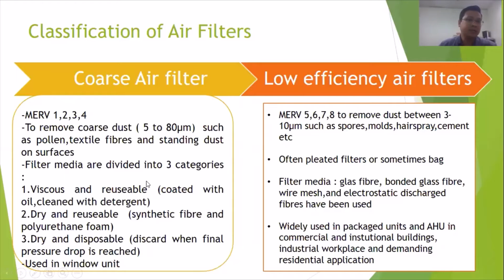The filter media is divided into 3 categories: viscous and reusable, coated by oil and cleaned with detergent; dry and reusable, made of synthetic fiber and polyurethane foam; and dry and disposable, discarded when the final pressure drop is reached, used in the window unit.